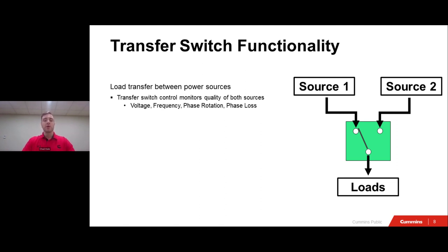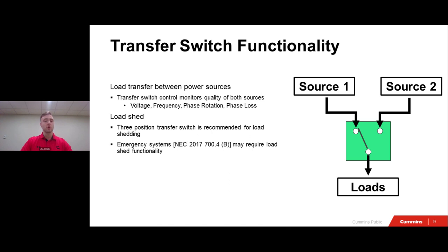If a source fails, the automatic transfer switch will go through the proper steps of transferring power from the normal source to the emergency source to restore power to the loads, those loads being things such as lights, exit signs, critical equipment, things like that. And then next, we have load shedding. Load shedding is when you have a transfer switch monitoring the alternate power source. If an overload event occurs, the transfer switch will start shedding the non-critical loads. Keep in mind that in this case, it is highly recommended to use a three-position transfer switch because you will have that neutral position or that center off position, which we will discuss later on in the presentation.